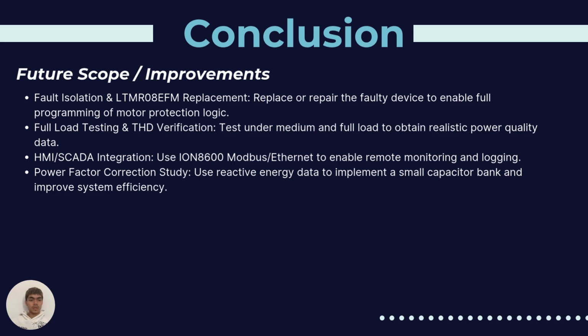So HMI card integration: use the power analyzer Modbus or Ethernet to enable remote monitoring and logging, which can be done as well in HMI. And power factor correction study: use reactive energy data to implement a small capacitor bank and improve system efficiency.